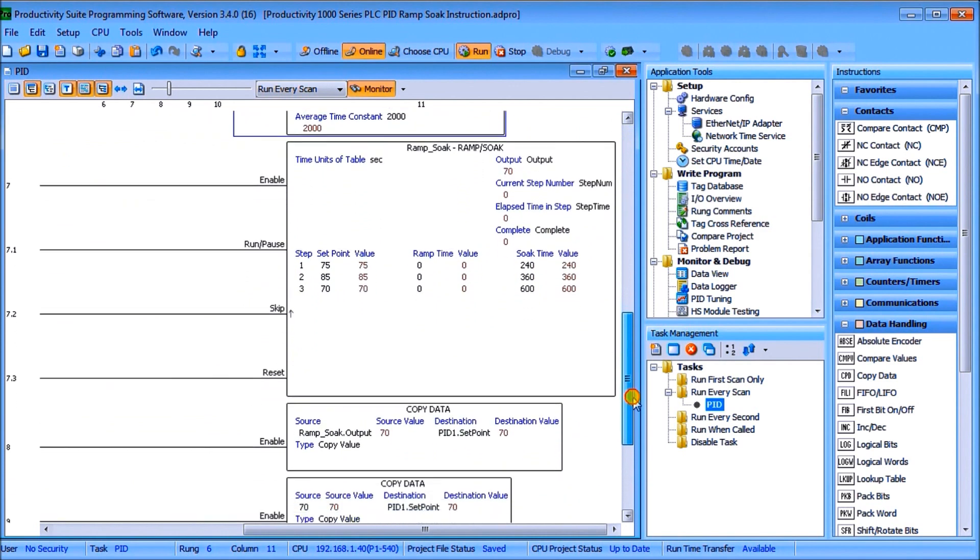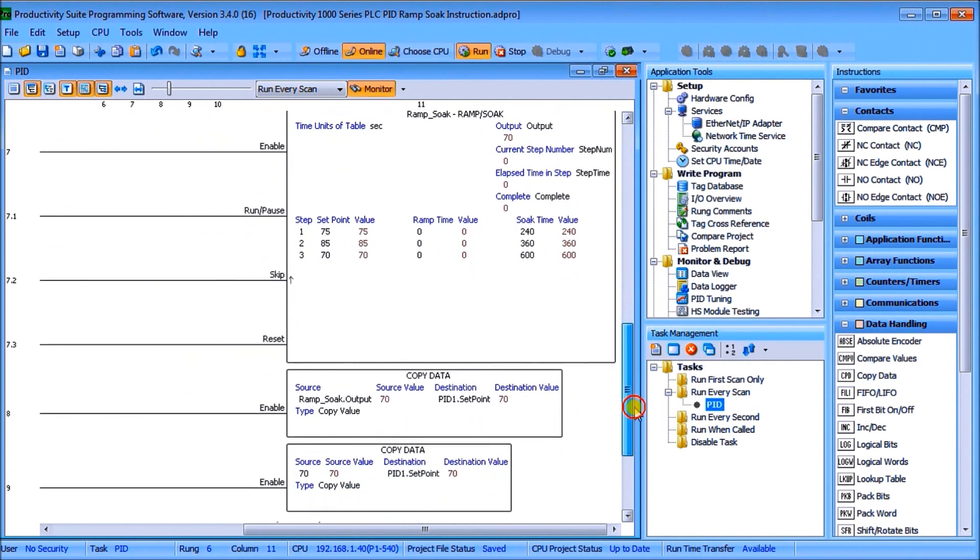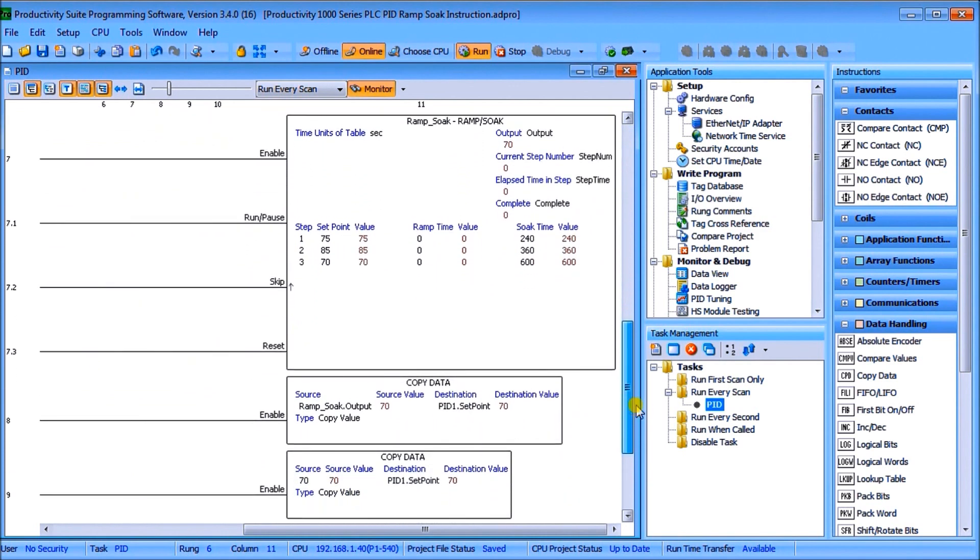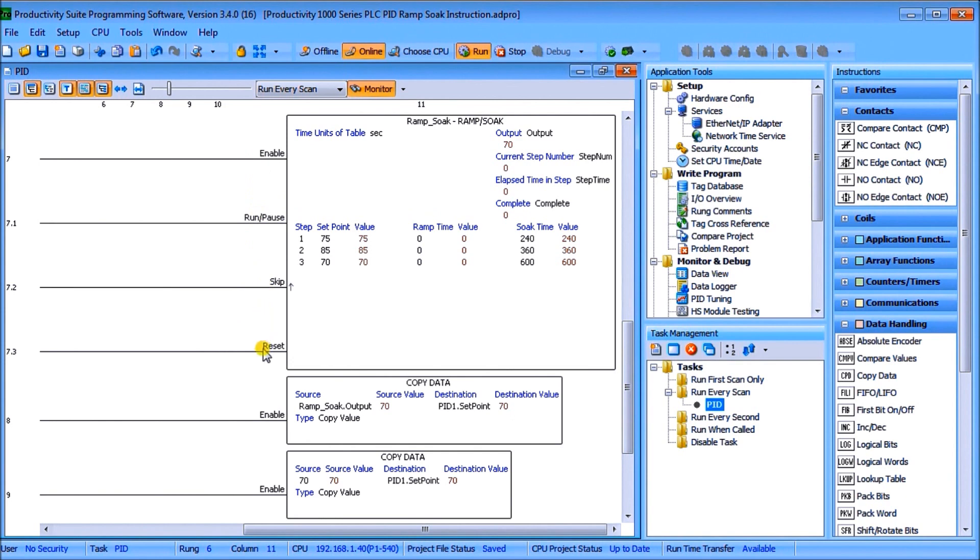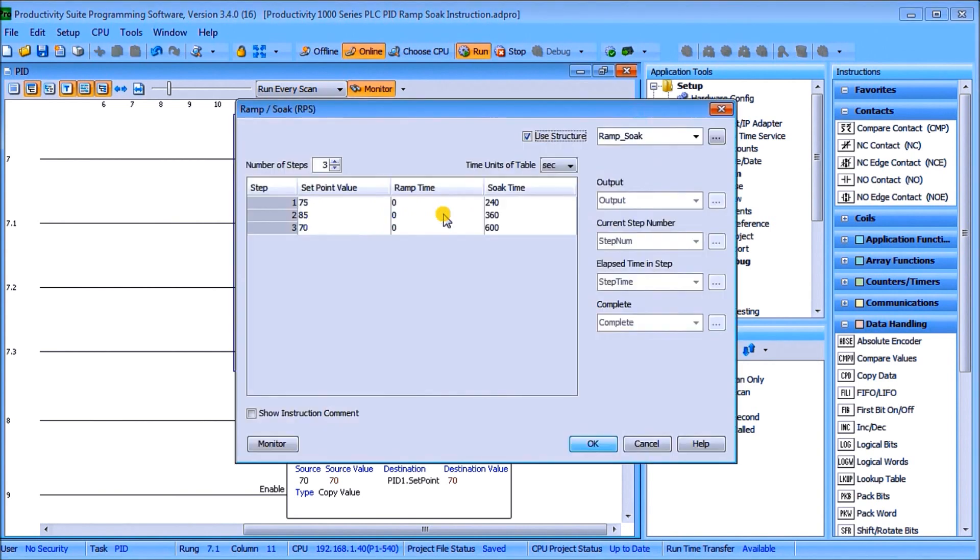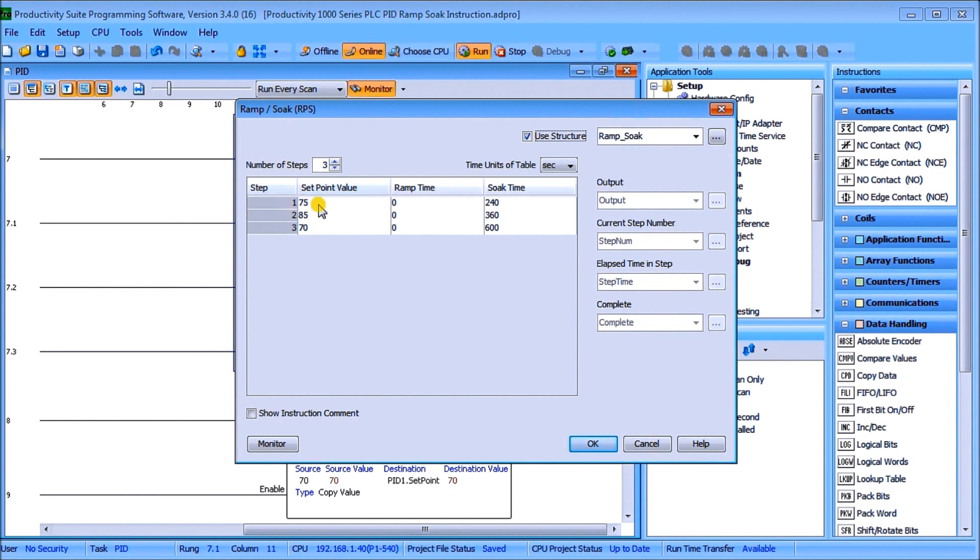So today we're going to actually take a look at the ramp soaking feature and you can see that we have four inputs: we have an enable, we have a run pause, we have a skip and we have a reset, and then we have our steps that we do. So the first step that we have is 75 so it's going to change the set point to 75.